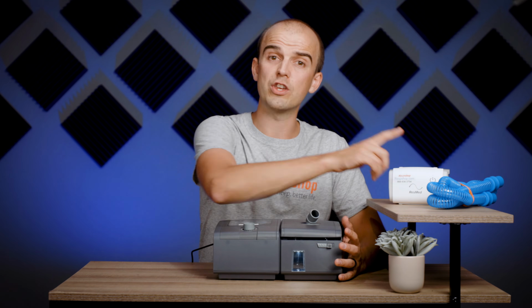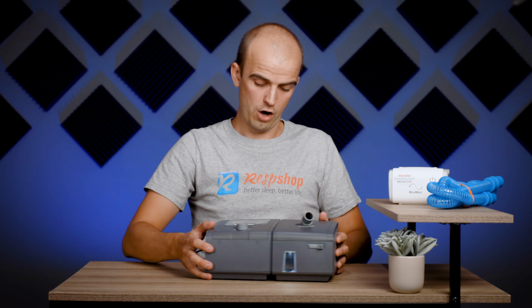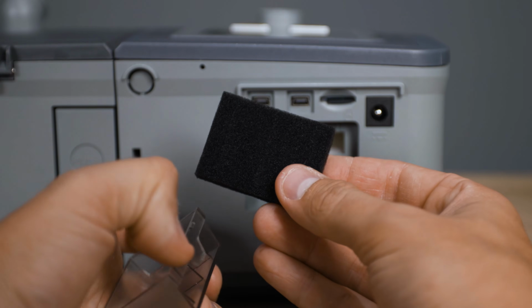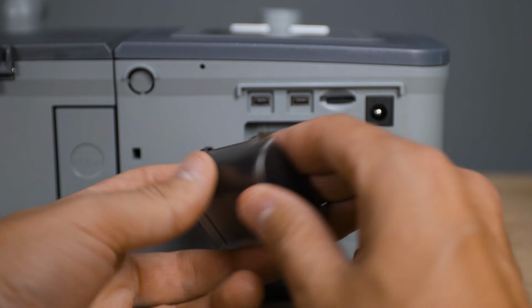And speaking of cleaning, you'll want to clean the humidifier weekly, along with whatever tubing you are using with the unit. Whenever cleaning these items, it's a good habit to also check the quality of the disposable foam filter, which is found at the back of the machine. This filter should be cleaned whenever dust is visible on its surface.